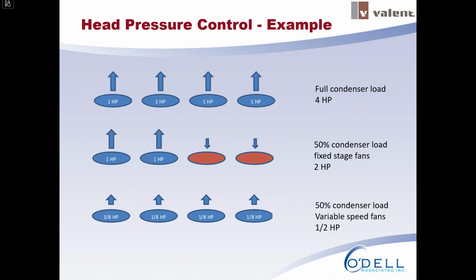And think about the condenser coil. You're not going to pull airflow evenly across that coil. Maybe one half's getting more and the other half's getting less. You're also short cycling air through those fans that are off, so not quite as efficient. In that third row, this is assuming still a 50% condenser load, but now let's pretend our fans all have that ECM setup. So we have EC motors, we're modulating those fans down, and we're able to still operate that same airflow, but at only using a half horsepower. So significant energy savings, and we're getting even airflow across that condenser coil. We're getting excellent heat transfer, very efficient. So having these higher efficiencies allow units to comply with relevant codes. And now Nathan's going to talk about these codes and relevant testing standards.